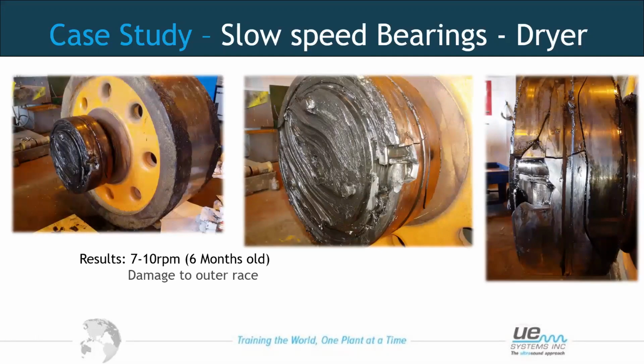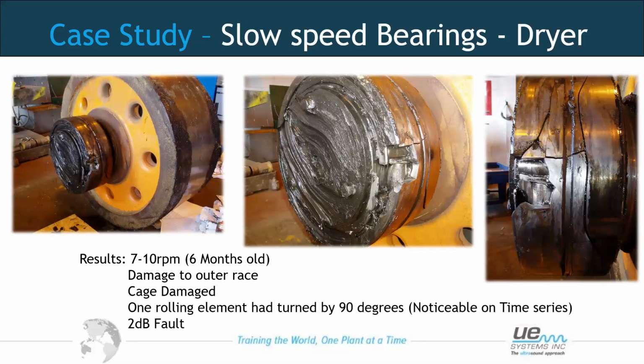As we can see from this bearing, there was quite a lot of damage. There was some severe damage to the outer race, and the cage had been damaged, where we can see one of the rolling elements had now moved by 90 degrees. And we could hear quite clearly the repetitive sounds from that bearing. So again, this was a great find because this would have had a severe impact on the site's production.